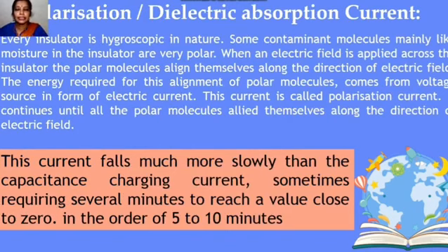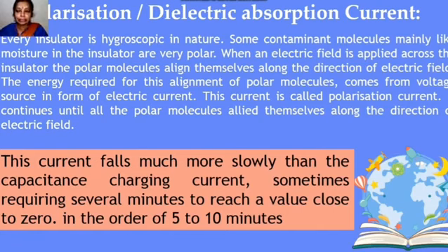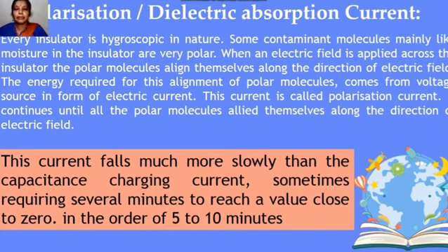The polarization current, also known as dielectric absorption current, arises because every insulator is hygroscopic. Contaminant molecules, mainly moisture, are polar in nature. When an electric field is applied, these polar molecules align themselves in the direction of the field; the energy for this alignment comes from the supply in the form of current. This polarization current continues until all polarized molecules align, typically taking 5 to 10 minutes, falling much more slowly than the capacitive charging current.